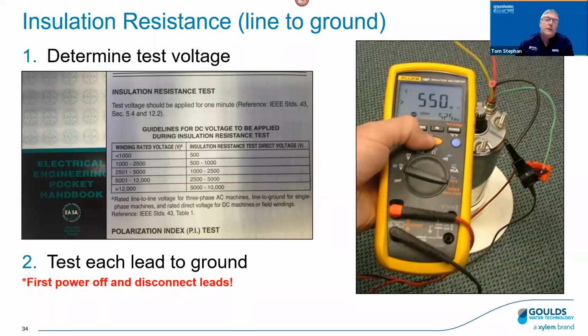Okay. So what happens if you want to use your brand new, in this case, Fluke 1587 insulation multimeter, which does everything for you? We've got to think about what voltage we want to use. See here, it says 500 volts. Well, if we look at number one, determine the test voltage. What voltage do you want to send through the windings, to pressurize the windings to see if it's grounded, right? So the book that we looked at earlier from EASA says if your winding voltage, the voltage of your motor, is less than 1,000 volts, test it with 500. Well, that makes it easy for us because these meters default to 500 and I don't need to change it, right? Perfect. I don't need to adjust that. I leave it at 500.